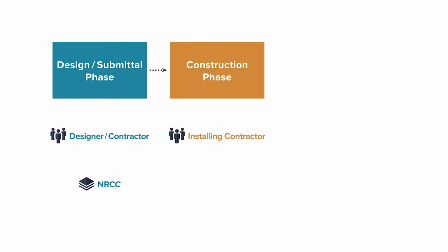Now that we're familiar with the different forms and people involved, let's tie everything together. The compliance process starts with the design and submittal phase. The designers or contractors on the project are involved in this phase and are responsible for completing the non-residential certificates of compliance, or NRCCs. The next phase is the construction phase. The installing contractors are involved in this phase and are responsible for completing the non-residential certificates of installation, or NRCIs.